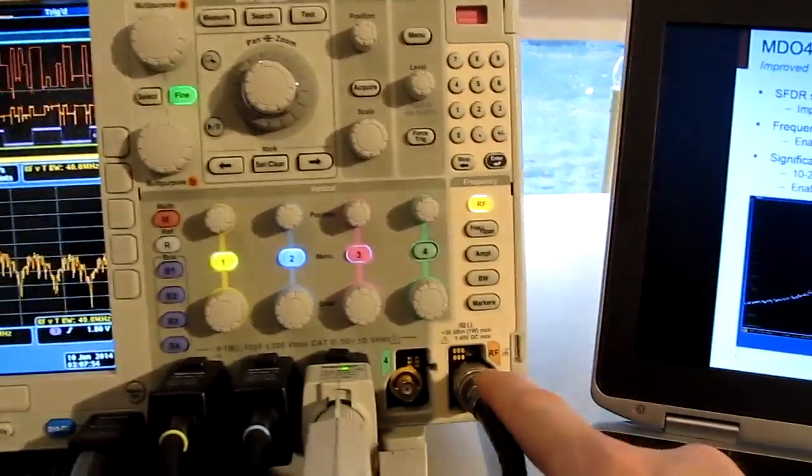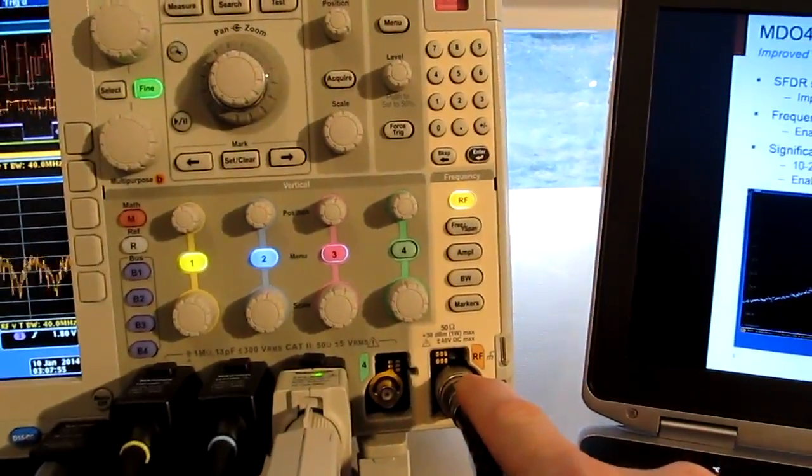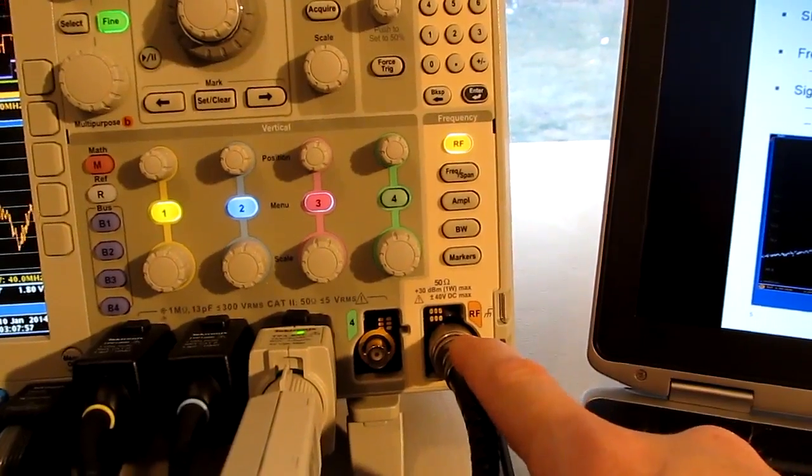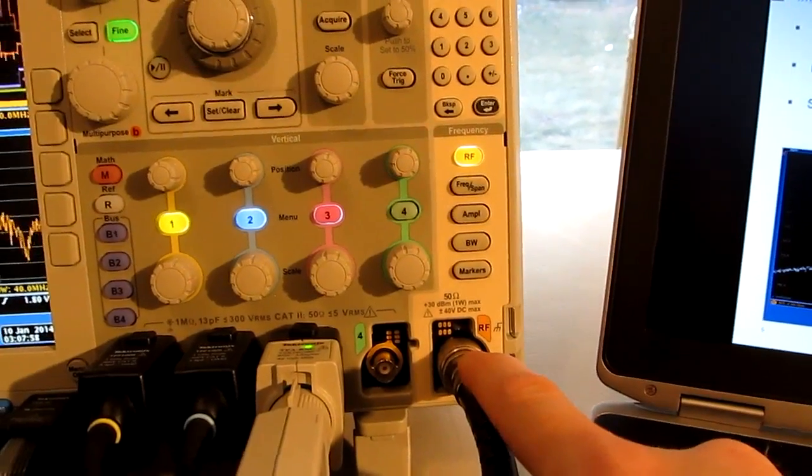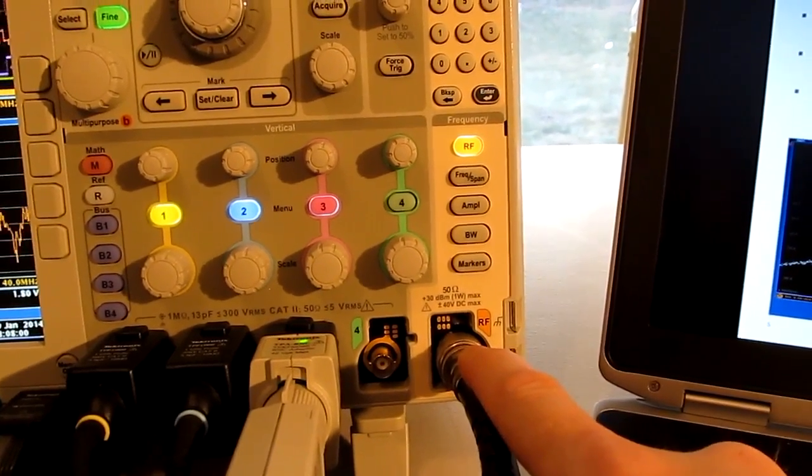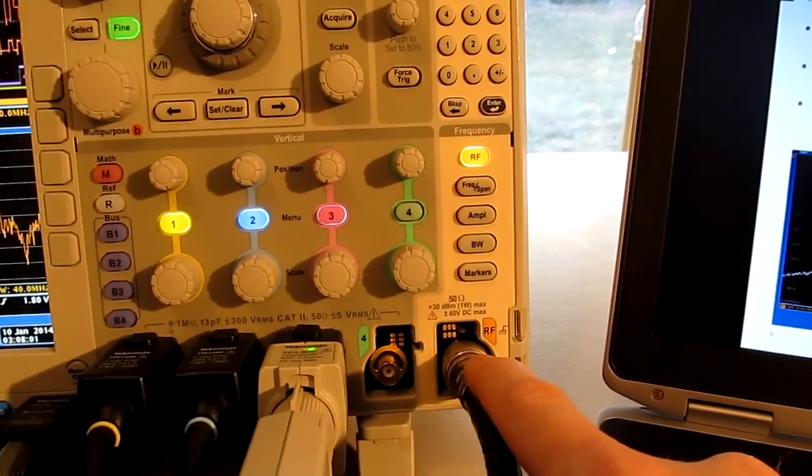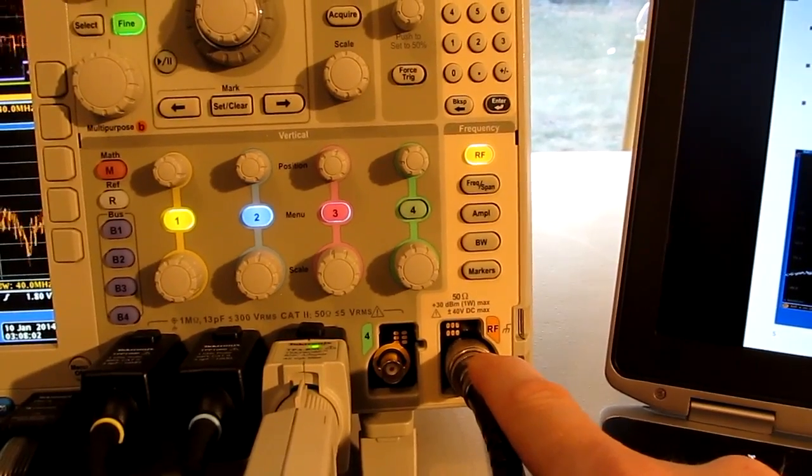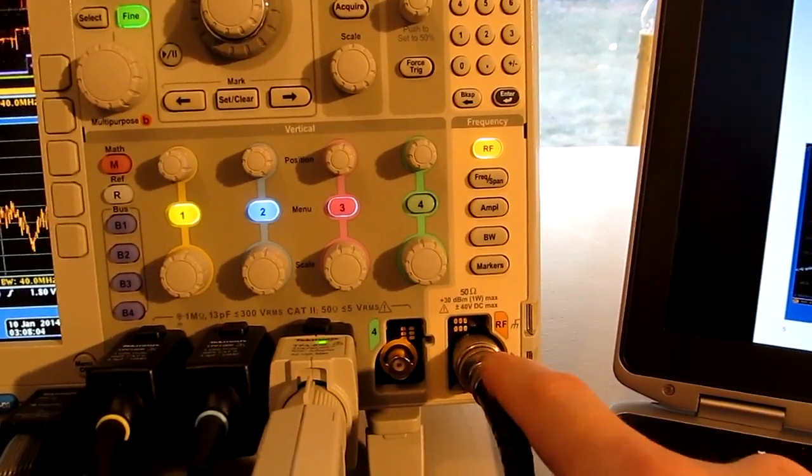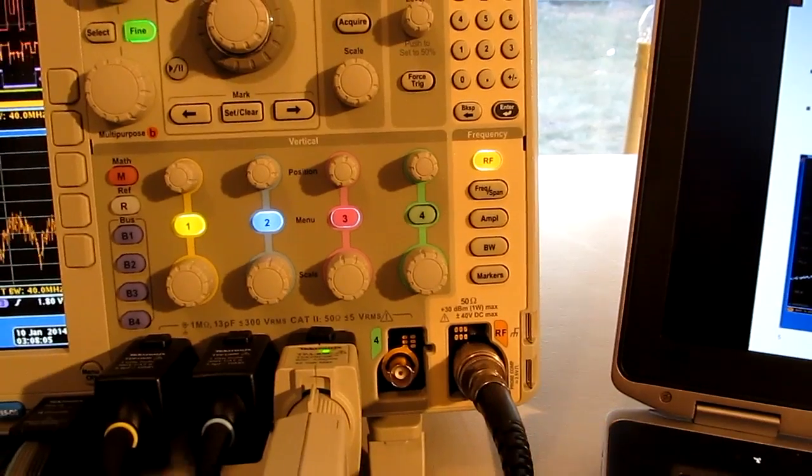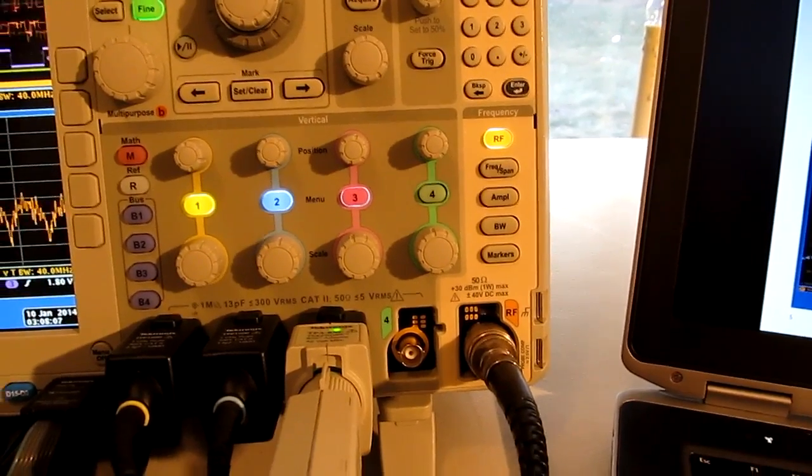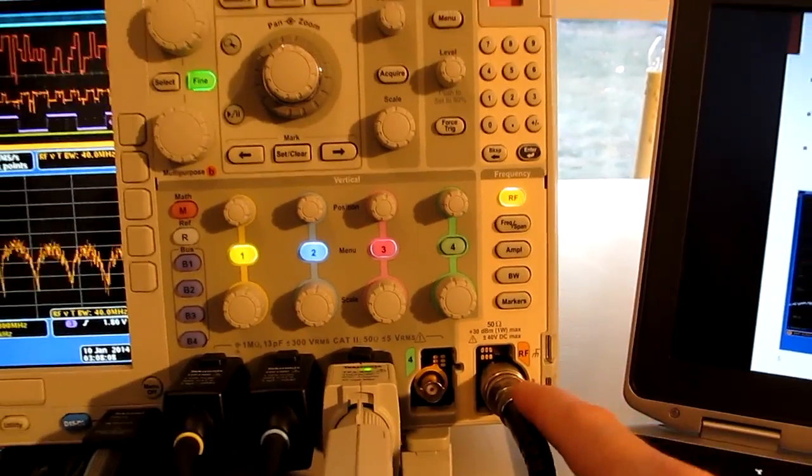The low frequency corner of the MDO previously was 50 kHz, that's been pushed down now to 9 kHz, and that's to better meet the needs for doing things like EMI diagnostic work.